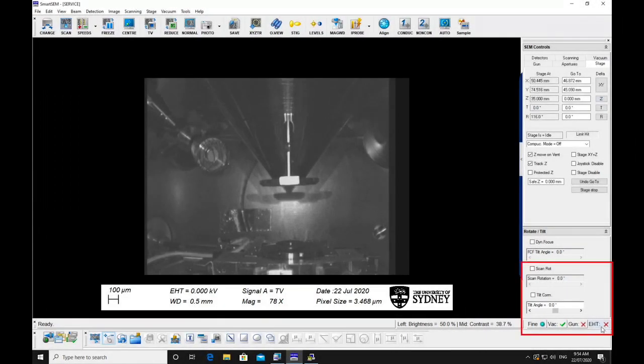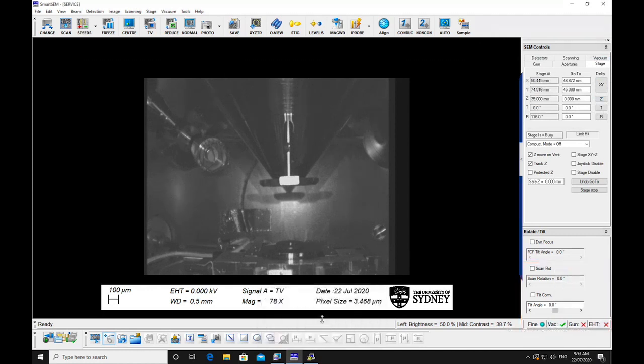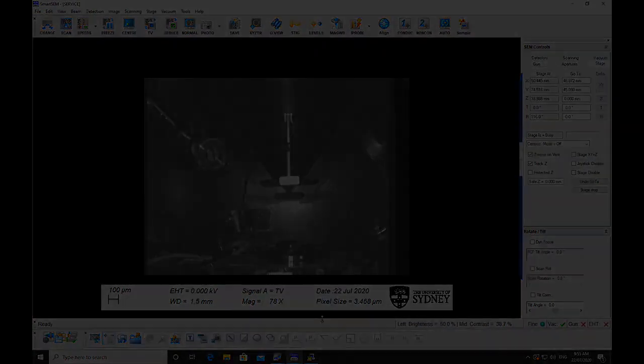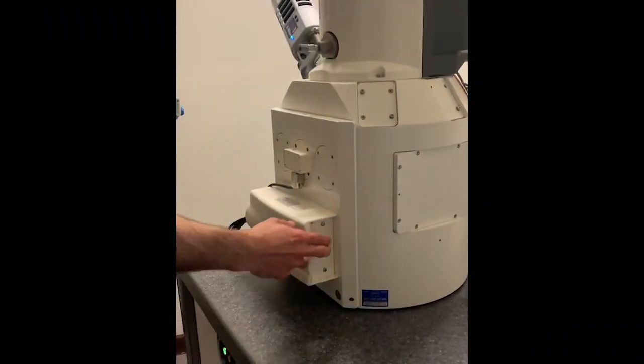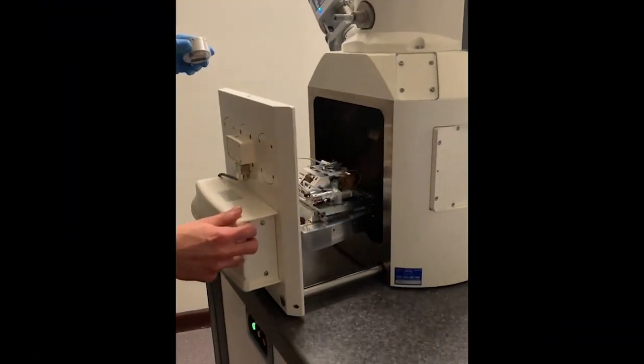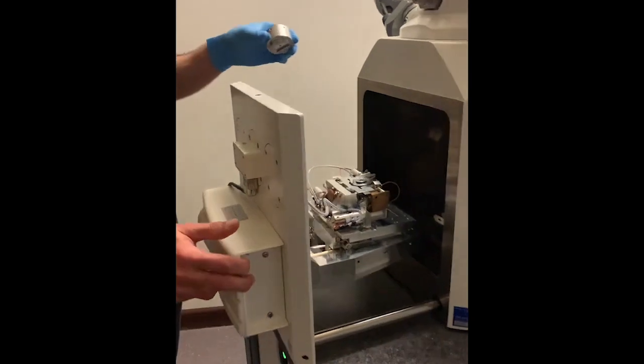Click on the VAC button and select Vent to vent the chamber. This will take a few minutes to vent. Once the chamber has vented, carefully open the door with your ungloved hand.